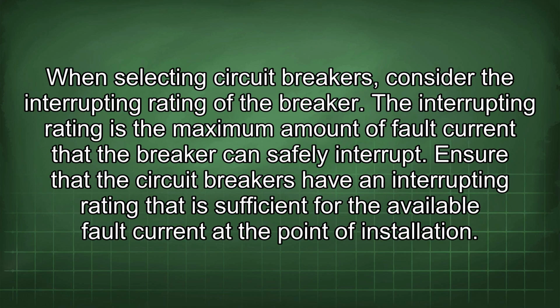When selecting circuit breakers, consider the interrupting rating of the breaker. The interrupting rating is the maximum amount of fault current that the breaker can safely interrupt. Ensure that the circuit breakers have an interrupting rating that is sufficient for the available fault current at the point of installation.